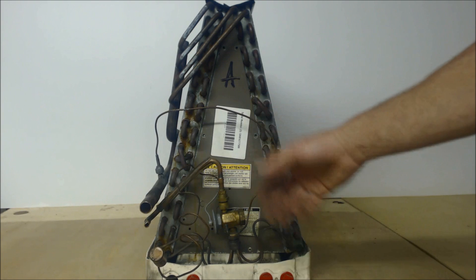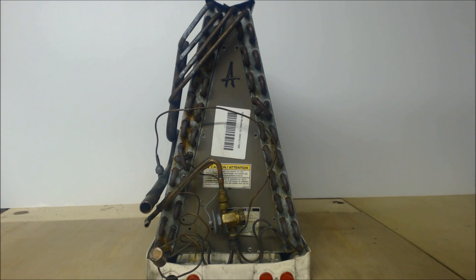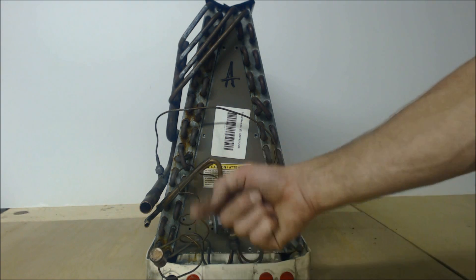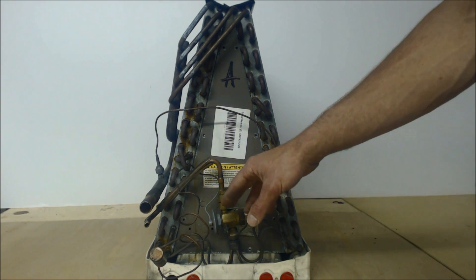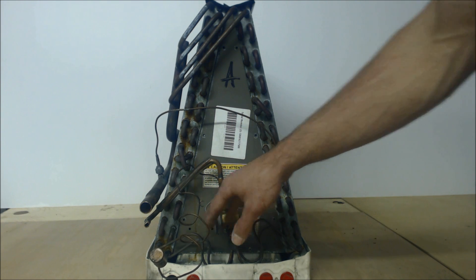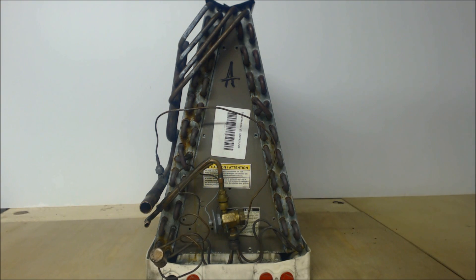Before checking a charge, make sure your filter is clean, you have good air coming out of the registers, and the blower motor is set to the capacity that this TXV and outdoor condensing unit are. Say the furnace is a 042 (42,000 BTU blower), and this is a 3.5 ton TXV and 3.5 ton outdoor condenser.